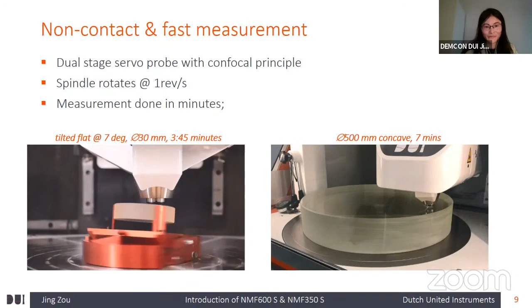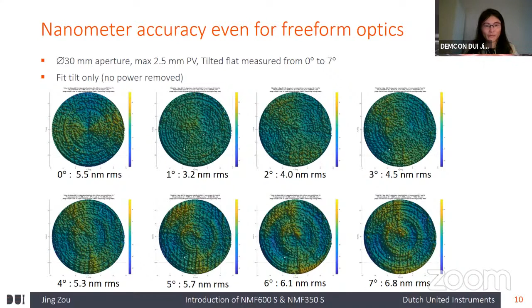And of course, the most important thing is performance, the accuracy. Since we do not have a standard freeform optics, we can measure a standard flat at different angles. So these are the results showing a flat piece measured at different angles from 0 to 7 degrees. The RMS value varied by about 4 nanometers. So it is very accurate, even for wild freeform optics.